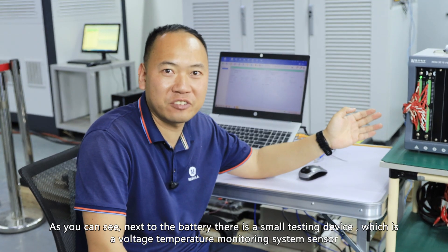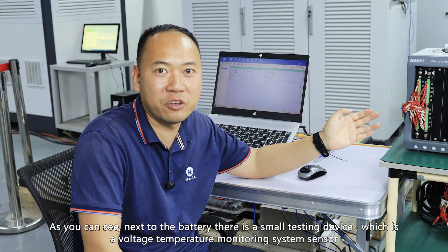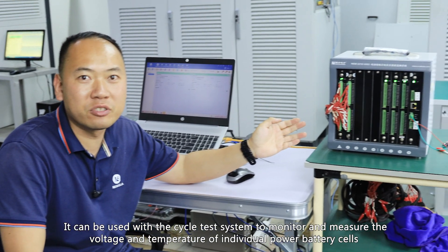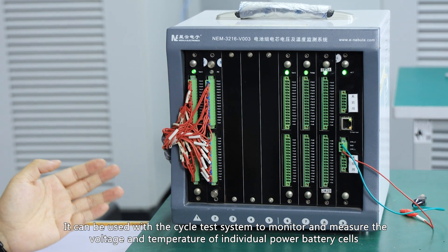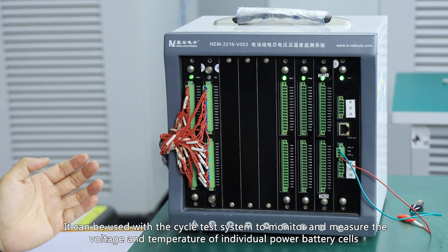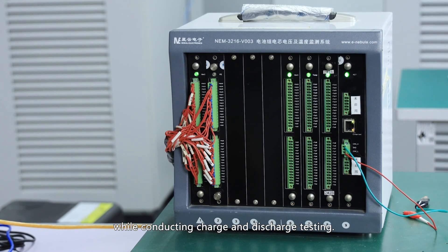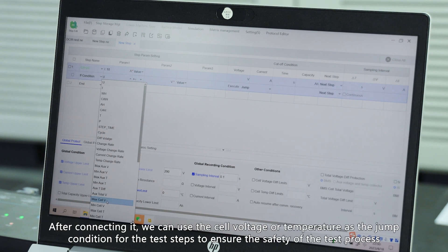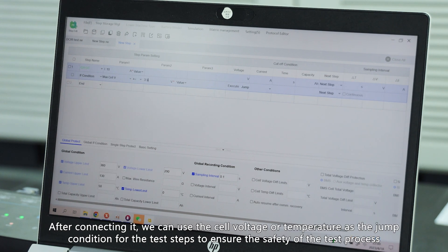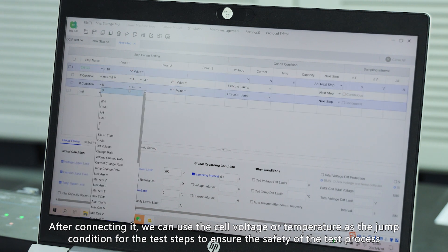The test system can also be used with a cell monitoring unit to measure the temperature and voltage of individual power battery cells while conducting charge and discharge testing. After connecting it, we can use the cell voltage or temperature as the jump condition for the test steps to ensure the safety of the test process.